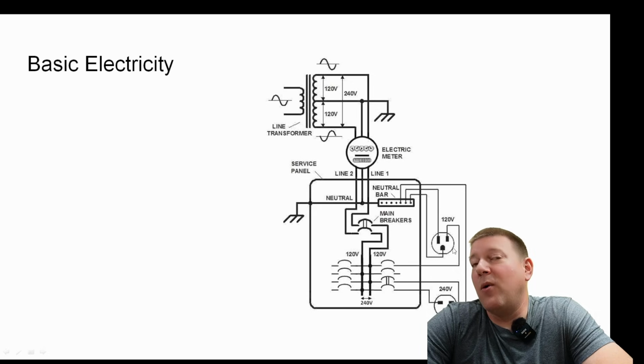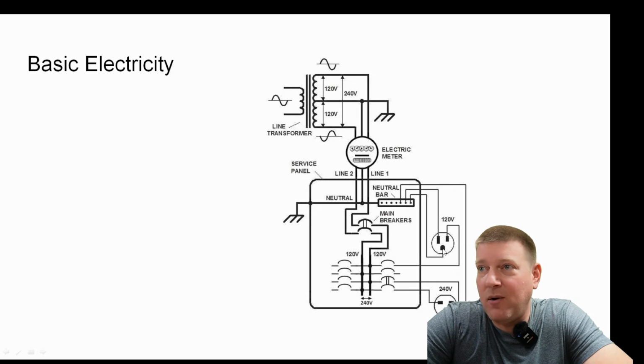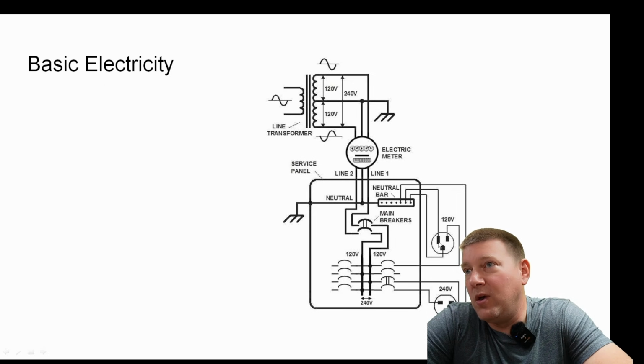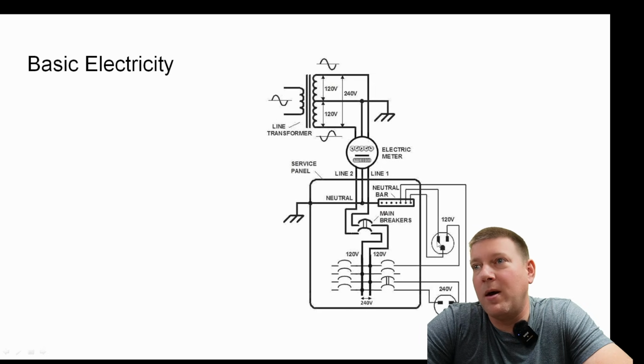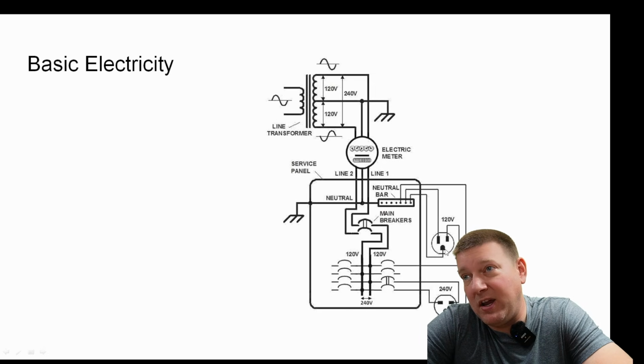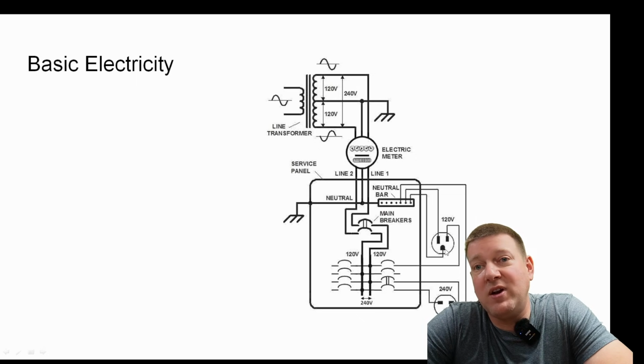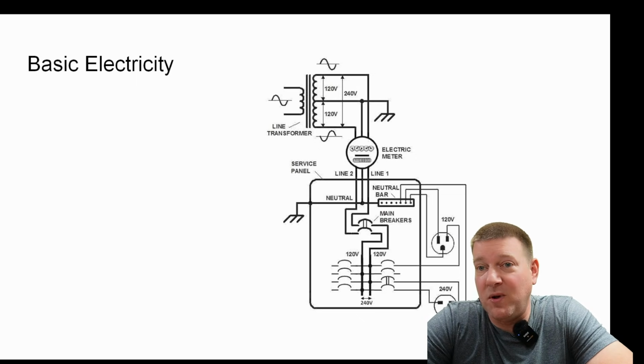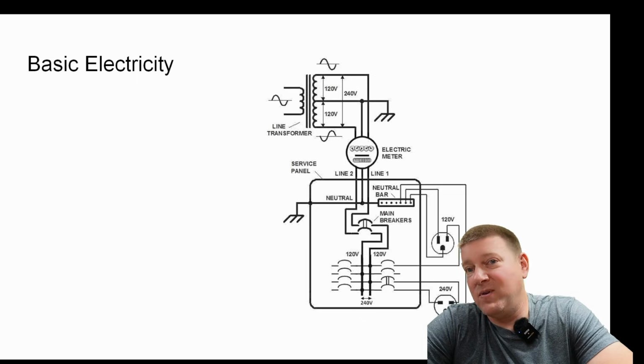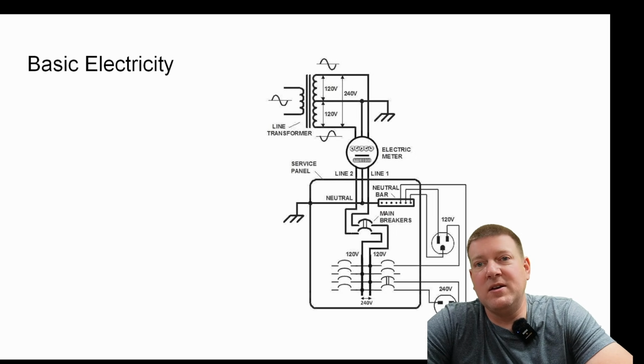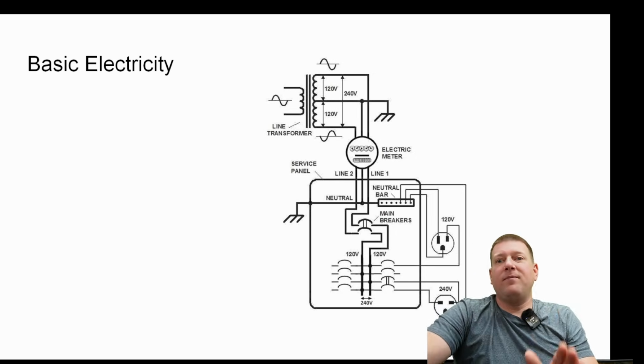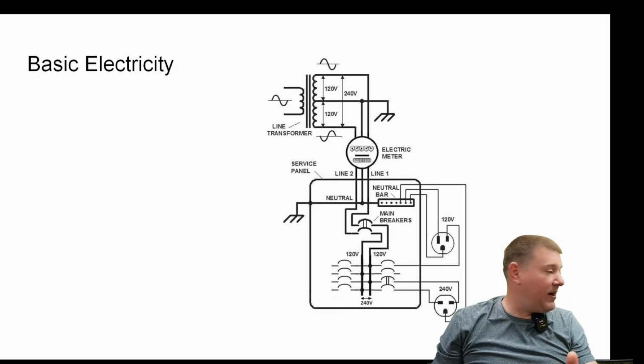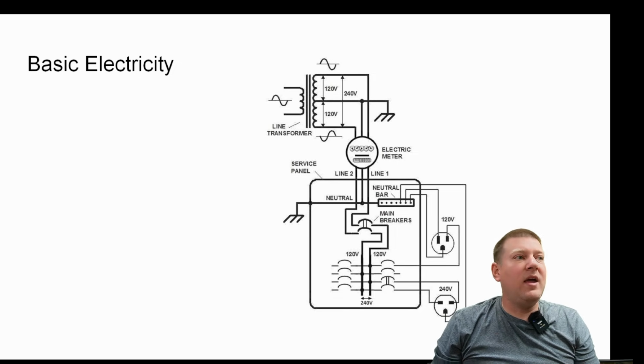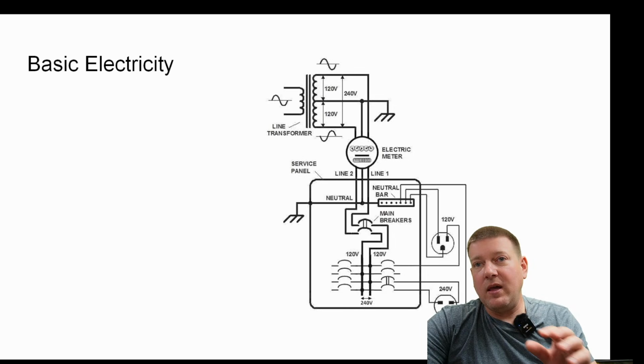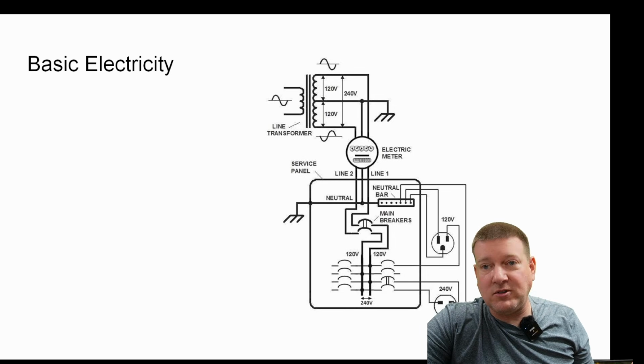So ordinarily, unless you're on isolated power, you should be able to go up to the large blade and the ground blade, measure across those, and you should have around about 0 volts. Now you're never going to have 0 volts, and that is because anytime you have a conductor, I could even have a coil of wire sitting right here. Anytime you have a conductor, there's electromagnetic spectrum everywhere.